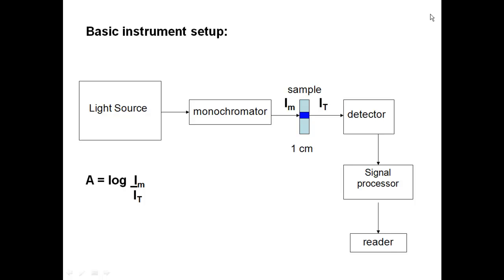Many setups are very similar to the one shown here. We have some light source that gives all the different wavelengths of light. That goes through something called a monochromator, which narrows down the wavelength to one single wavelength of light. Then we can measure that intensity of light before it goes to the sample.